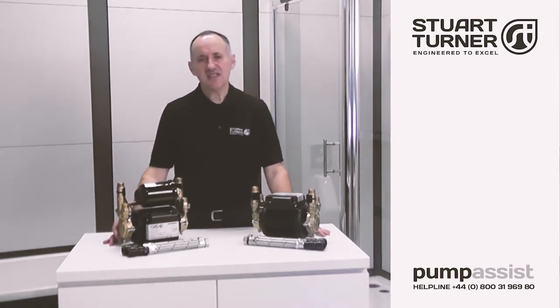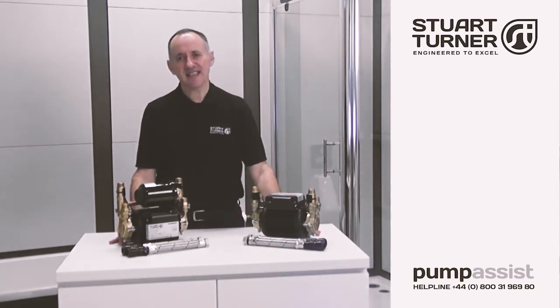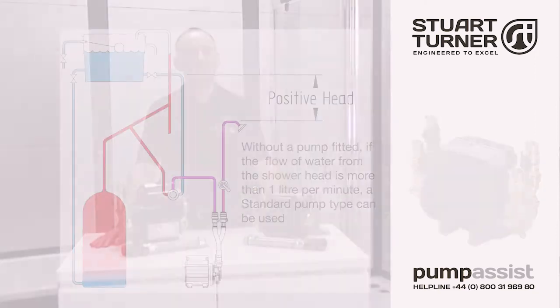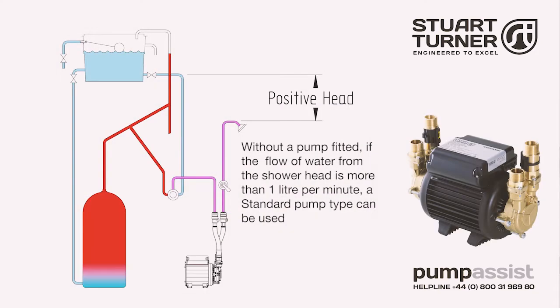The key decision is understanding whether you need a standard or a universal pump. The standard pump uses a flow switch that reacts to natural gravity flow and will activate the pump when the shower valve is opened. If the flow from the shower head due to gravity alone is less than a litre a minute, for example a dribble or a trickle, then a standard pump will not start.